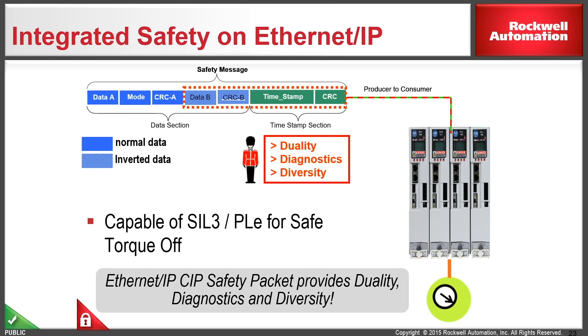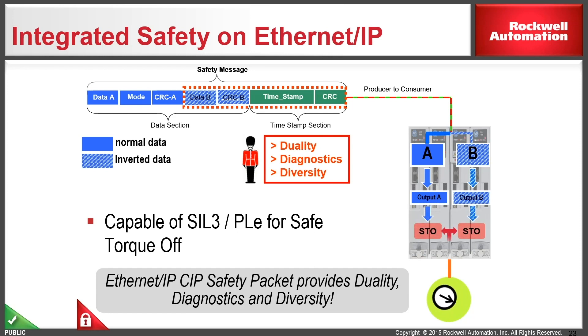This all gets packaged up into a message, gets sent down over to the drive, and at the drive level there are two separate processors, one looking at data A, the other looking at data B. They basically solve their logic, look to see what the output state should be. They then compare that information. If they match, the drive goes into safe torque off mode or run mode depending on what the drive was being told to do. If the messages happen to differ or there's an issue with the checksums or the message somehow gets corrupted, the drive would then fault and go to the safe state.